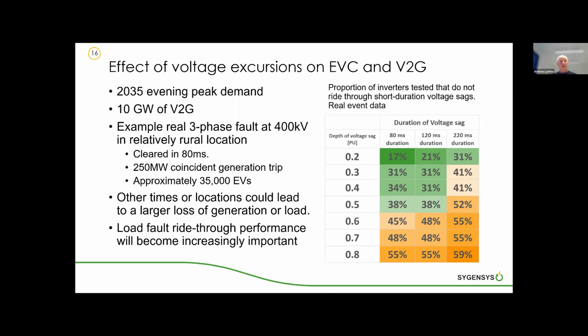And this is a concern in terms of the way in which the ride-through performance for grid-connected devices is defined, both in terms of load and generation. And within the report, we highlight some great work that has been done within Australia, looking at PV inverters, highlighting that quite significant proportions of inverters end up disconnecting, even for relatively short and relatively small voltage sags. And part of the issue here is that those voltage sags may combine both a voltage change and a phase change at the same time. And Martin will talk much more about this later on.